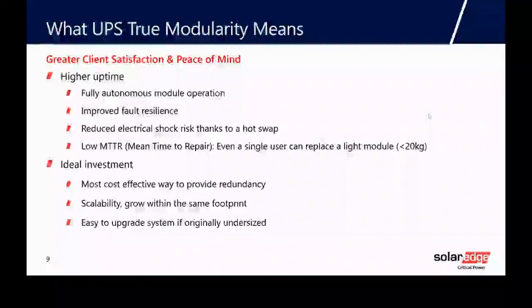Obviously, improved fault resilience, reduced electrical shock risk. In the old days, you had people inside these UPS systems, which have very high AC and DC voltages. But now the engineers just swap a module, so their risk of electrical shock is a lot less. Low MTTR is very key. Obviously, it's a critical system, you want it to be up and running all the time, so if you can fix it very quickly, that's a big bonus. And it's a good way to invest.